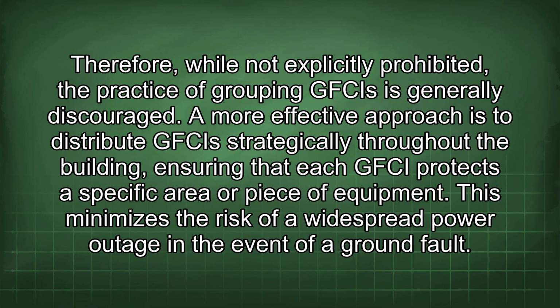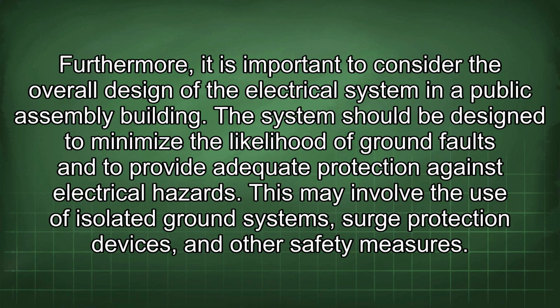A more effective approach is to distribute GFCIs strategically throughout the building, ensuring that each GFCI protects a specific area or piece of equipment. This minimizes the risk of a widespread power outage in the event of a ground fault. Furthermore, it is important to consider the overall design of the electrical system in a public assembly building. The system should be designed to minimize the likelihood of ground faults and to provide adequate protection against electrical hazards. This may involve the use of isolated ground systems, surge protection devices, and other safety measures.